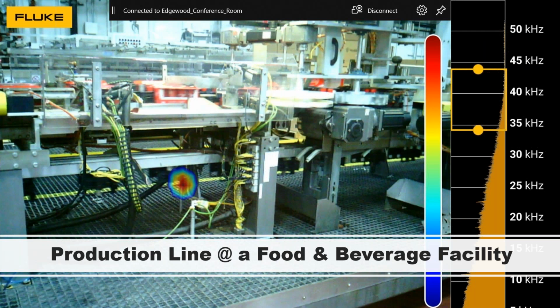I'm not going to tell you how much compressed air food and beverage processing uses, but every time I've been in one, bottling plants, packing plants, we've always found stuff. And you wouldn't think one little leak is a big deal. It's not costing me that much money. But when all of your equipment runs on compressed air, if you've got 150 leaks in that facility on any one day, that's significant compressor cycling and usage, which means you're paying for it in extra kilowatt hours. You're paying money for that every year, and it adds up.